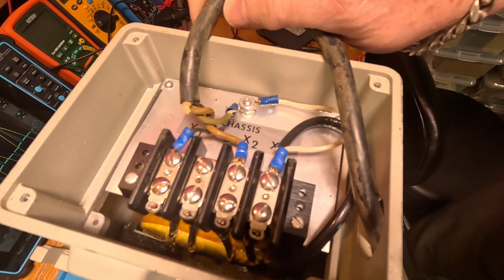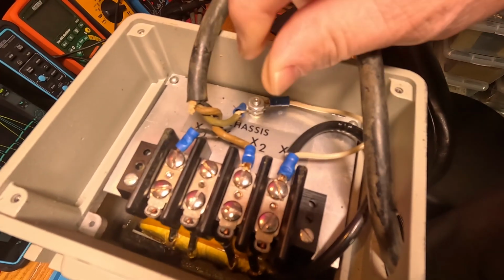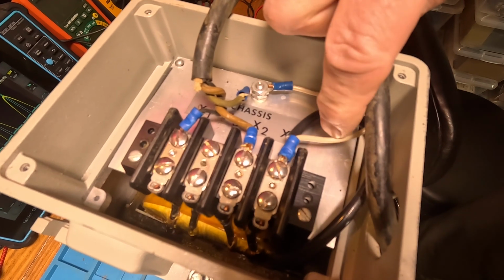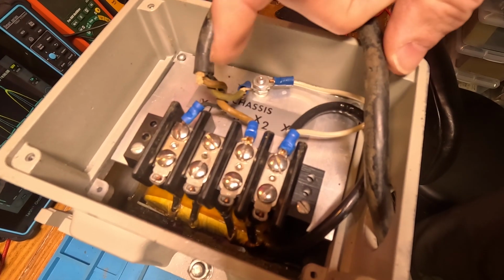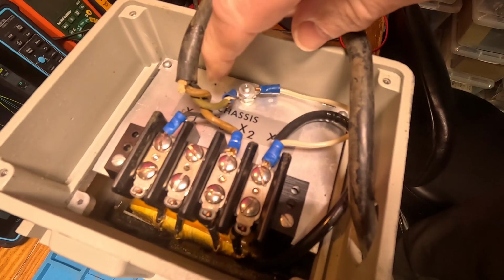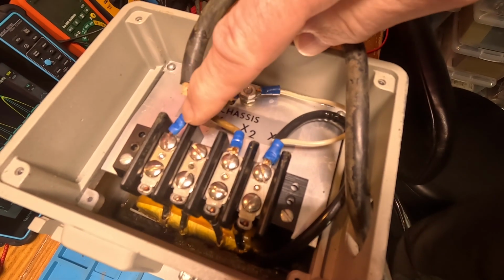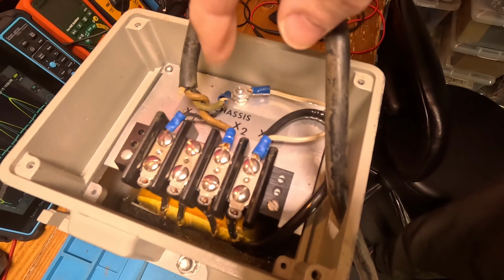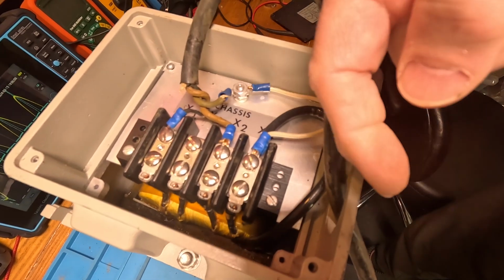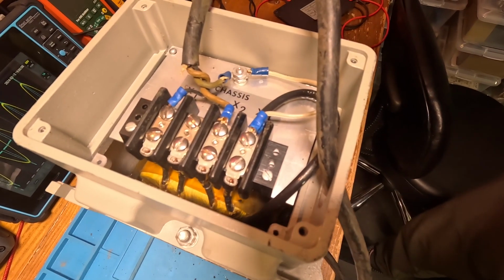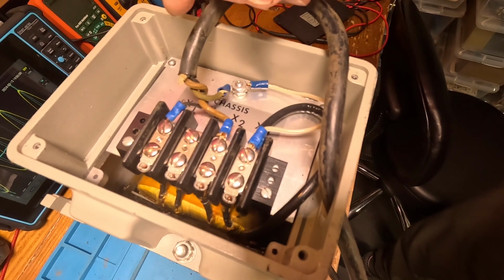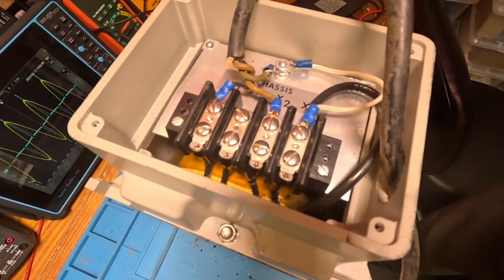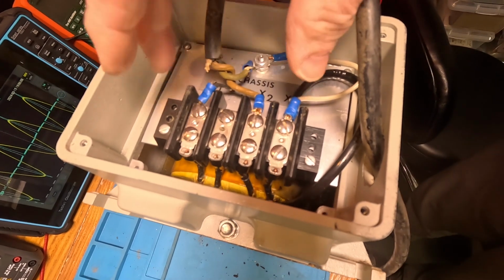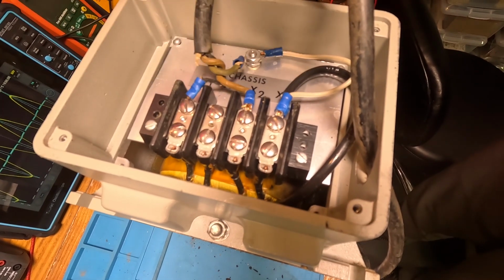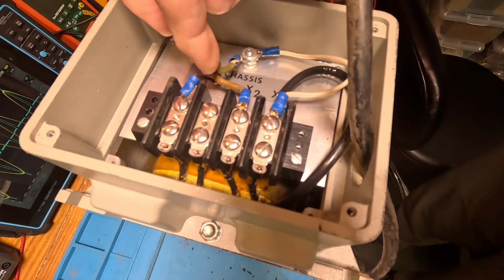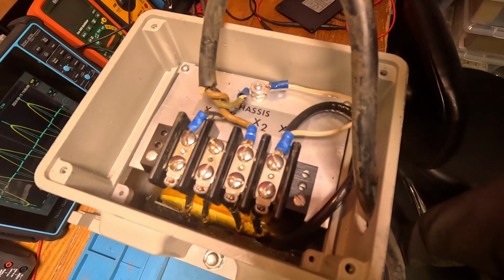It's really curious, almost like if the neutral shorted, or if the inside of the windings shorted to ground or chassis, then all the current would go through the black wire into the chassis. It'd probably be shared between neutral and ground going back to the power cord, or maybe pop the breaker. That makes me curious and worried about this transformer. For 240 you'd put them in series, but for 120 they should have been in parallel, and they definitely didn't do that. That makes me worried.